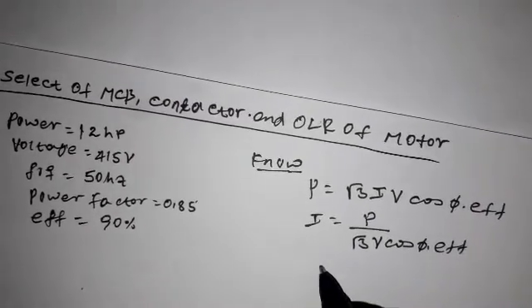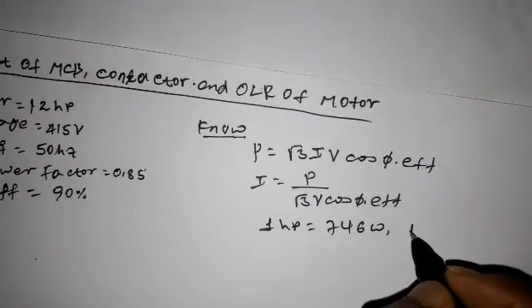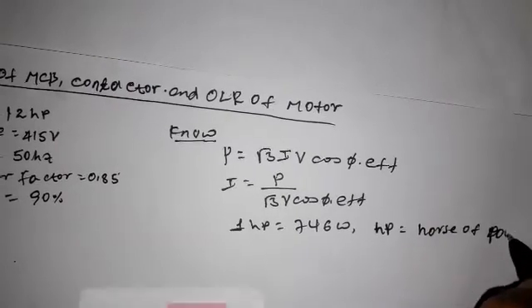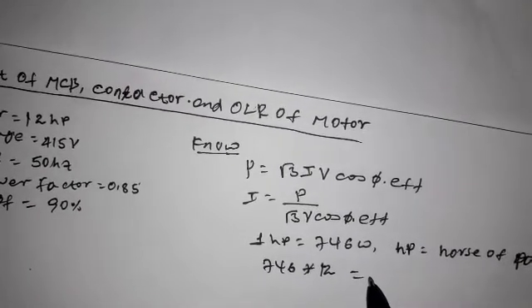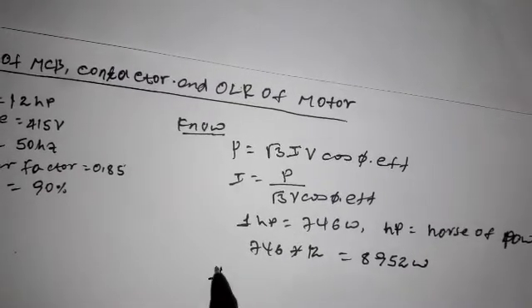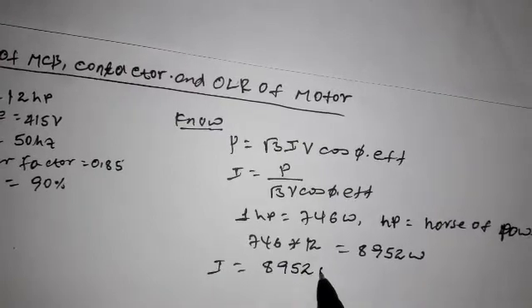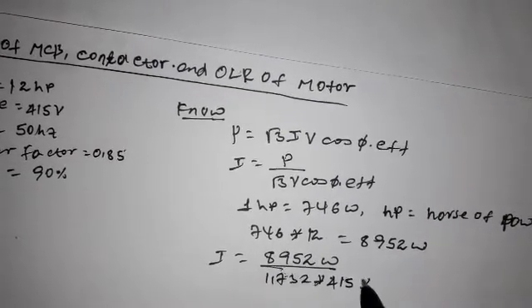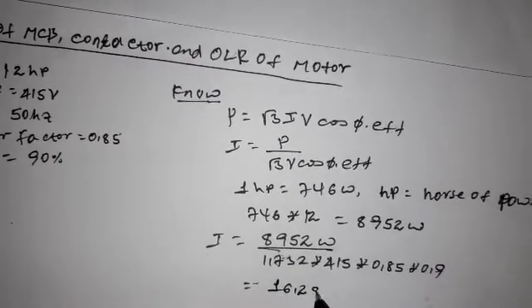Then, 1 hp is equal to 746 Watt. HP means horsepower. Now, 746 times 12 is equal to 8952 Watt. Current is equal to 8952 Watt divided by 1.732 times 415 times 0.85 times 0.9 efficiency. Current is equal to 16.28 Ampere.